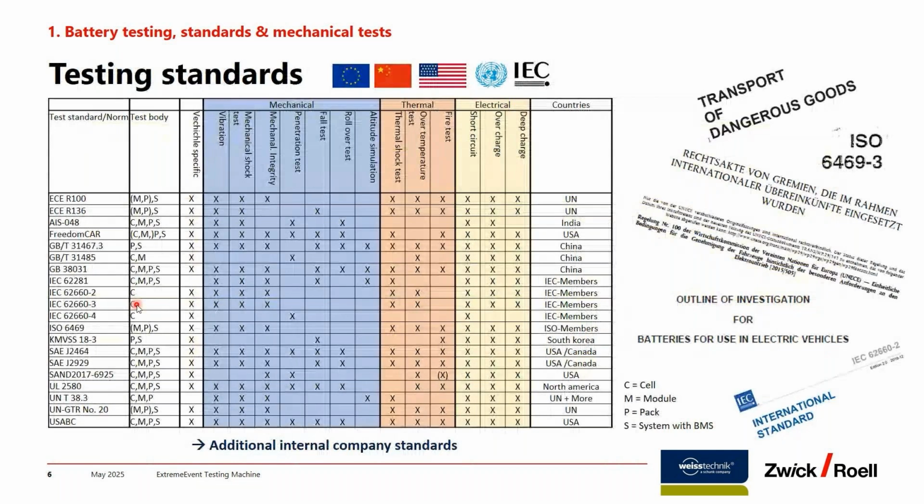Most of the testing standards are shown here, an overview of the testing standards that we get from our customers. Most of the well-known standards are the ECE R100, which you will see here on the top, then the IEC standards, as well as the UN 38.3 standard.